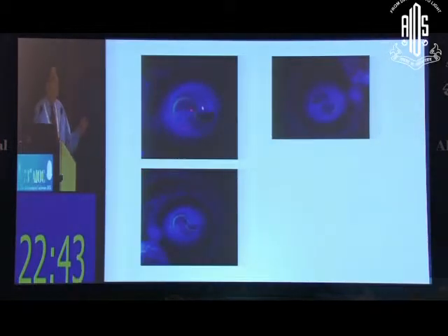So these are the correct widths of the mires. You can see the superior one and the inferior one, both are in equal proportion to each other, and you join the inner margins of the two half rings here. This one is not correct because the superior mire you can see is smaller. Here the inferior mire is smaller.